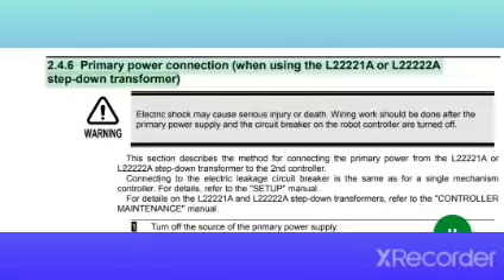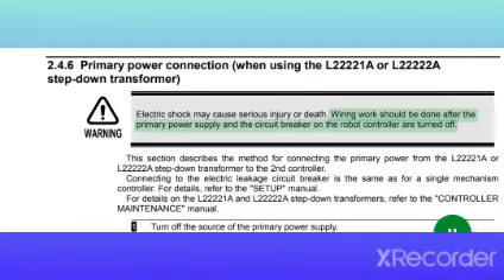2 to 23. 2.4.6 Primary power connection when using the L22221A or L22222A step-down transformer. Warning. Electric shock may cause serious injury or death. Wiring work should be done after the primary power supply and the circuit breaker on the robot controller are turned off. This section describes the method for connecting the primary power from the L22221A or L22222A step-down transformer to the second controller. Connecting to the electric leakage circuit breaker is the same as for a single mechanism controller. For details, refer to the setup manual.